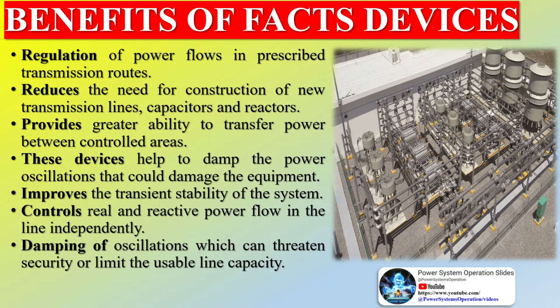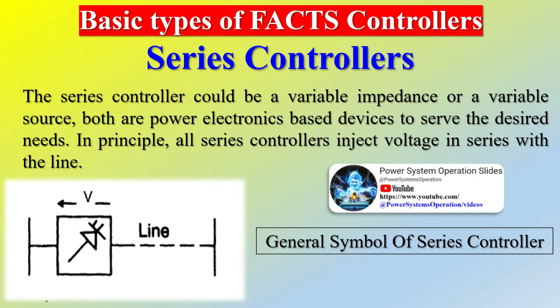Series controllers provide independent series reactive compensation for each line, but also transfer real power among the lines via the power link — the interline power flow controller. The combination could be separate series and shunt controllers or a unified power flow controller. In principle, combined shunt and series controllers inject current into the system with the shunt part and voltage in series with the line with the series part.